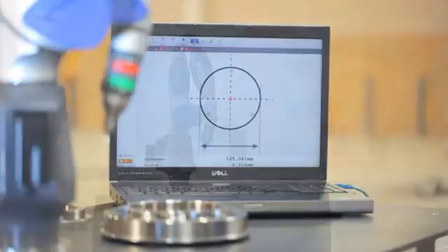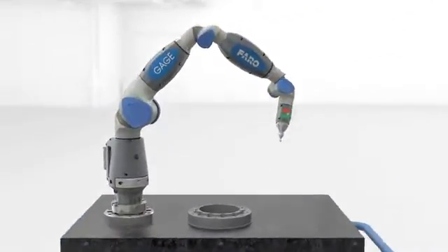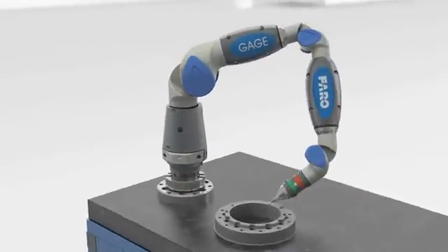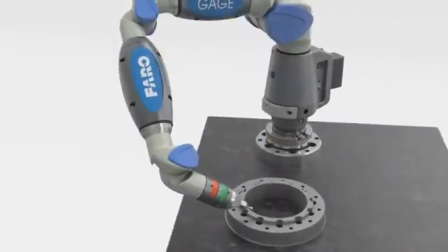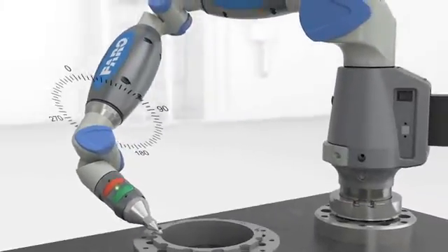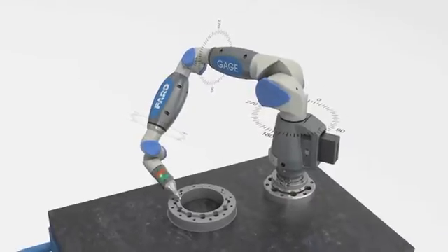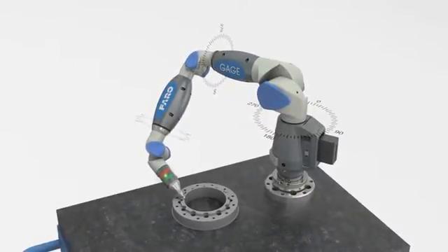It's easy to understand how the FARO Gage works. First, there's a probe at the end of the gauge that takes measurement points on command. A user simply clicks a button to record a point and special encoders compute the exact position of the probe within a three-dimensional space. This point is recorded in the software and the user moves on to take another measurement.